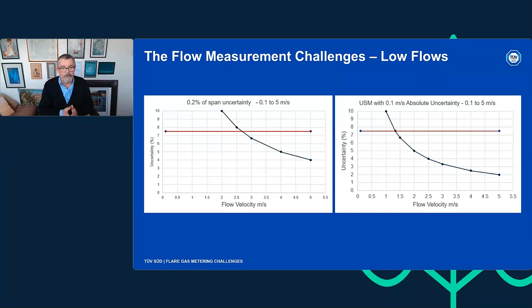On the left there, you can see that the uncertainty of the analog loop itself becomes significantly larger as the flow rate decreases because it's a percentage of span. So we can see there that anything below 2.6 meters per second and my analog loop uncertainty is already 7.5%. And if I look at the ultrasonic meter, again, a high quality ultrasonic meter with a 0.1 meter per second absolute uncertainty, in this particular case, any flows below 1.3 meters per second, and my absolute uncertainty from the ultrasonic meter is already 7.5%. And if I go lower, they get bigger and bigger exponentially.